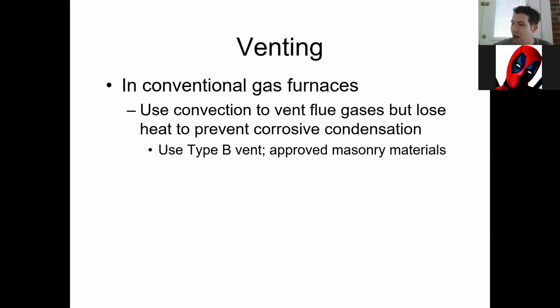So she's out. But the big thing with gas furnaces is that depending on the temperature of the flue gas, that's what's going to change the type of venting you're going to need. Old school furnaces that weren't super efficient used a very thin-walled venting called C-vent. It was very, very cheap and very easy to install. It's still used on some 80% furnaces nowadays.